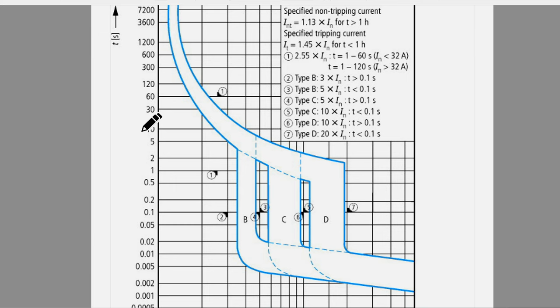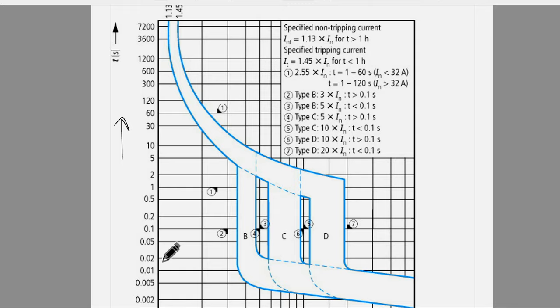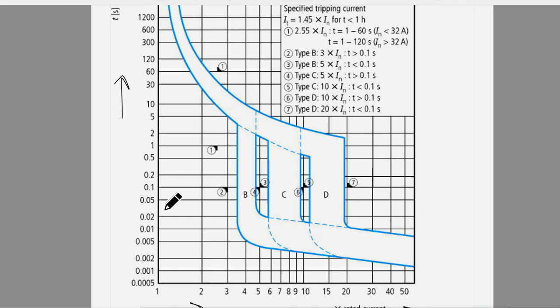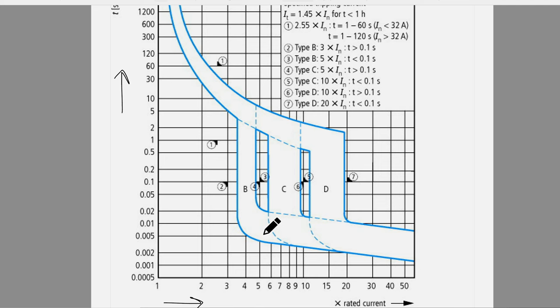Here's a diagram of different tripping curves on the same set of axes. The vertical axis shows the time it takes the circuit breaker to trip, and the horizontal axis shows the percentage increase in rated current. At rated current, most circuit breakers shouldn't actually trip — they trip at a higher current than the stated rating. At two times the rated current of a 10-amp breaker — so 20 amps — it could take about 25 seconds to trip. When talking about inrush currents, these are typically below 10 milliseconds, so we're interested in that fast section of the tripping curve.